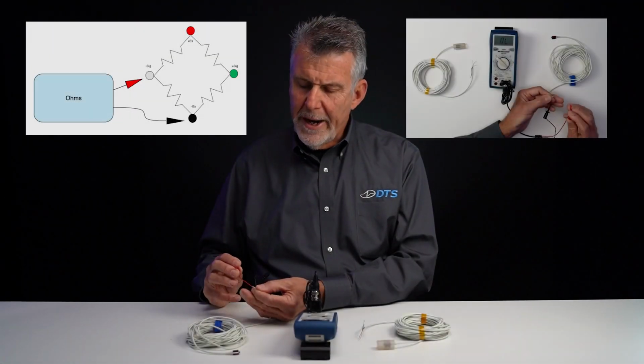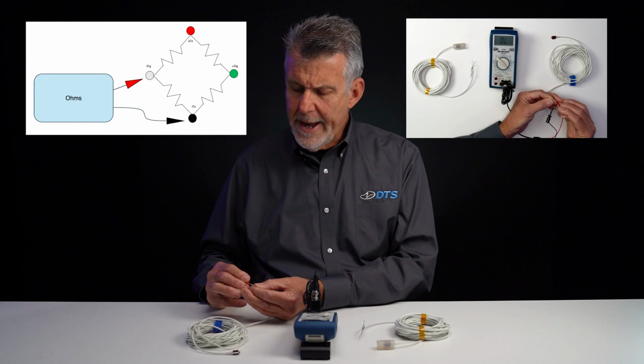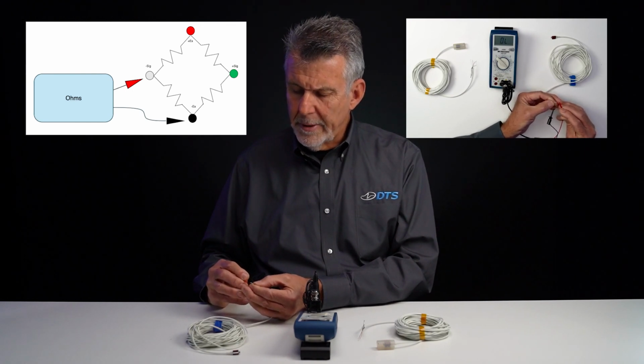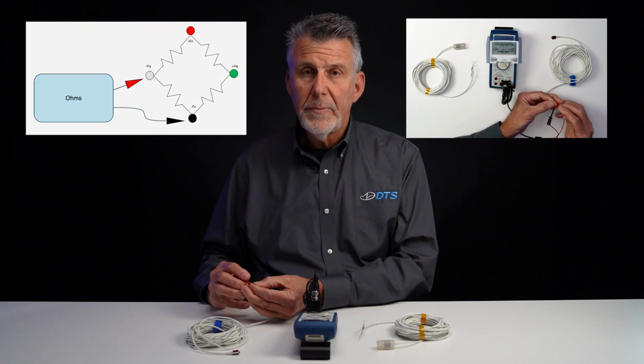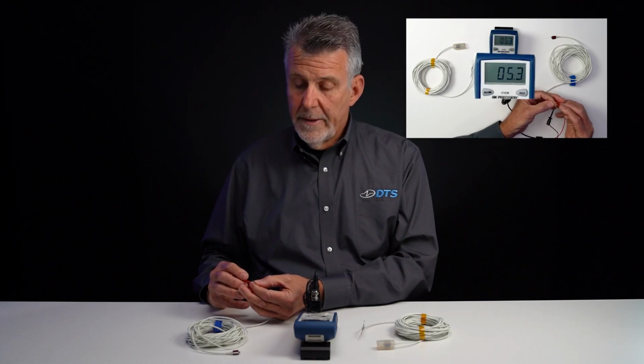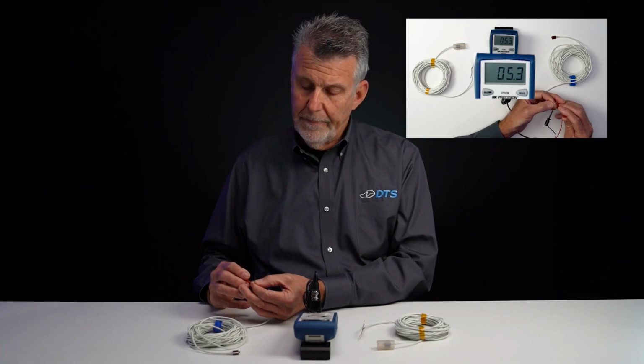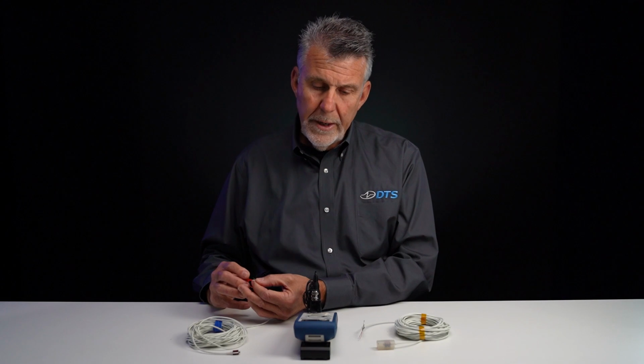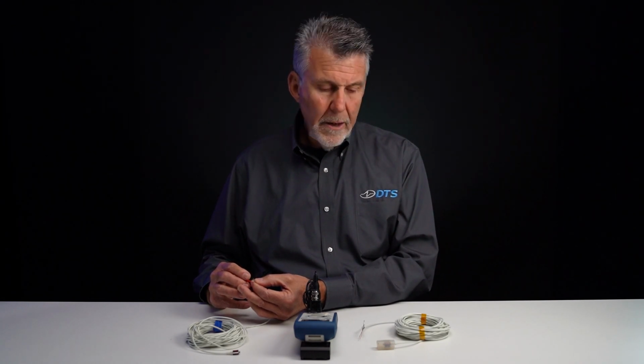Now I'm going to measure between the minus excitation and the minus signal to see what I get. And I'm expecting a number close to 6.3 kiloohms if the bridge is balanced, but I get a number of 5.3. This is very different than the 6.3 kiloohms and indicates a large imbalance in this half of the bridge. This is very likely the cause of the offset and shunt failure. Another thing I note is that the resistance reading is much higher when I go between the signal leads and the excitation leads than I did on the working sensor. And so to me, that's another clue that the sensor has been damaged or otherwise compromised.